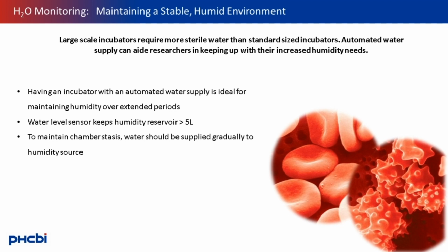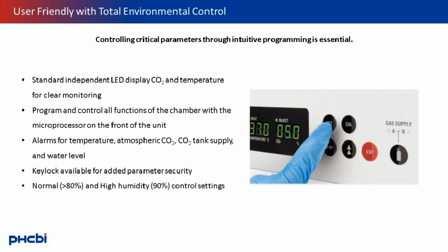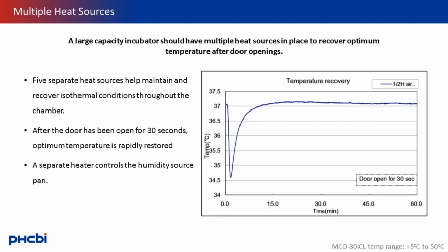Adjusting the levels for the humidity source can be done easily from the front of your incubator. It's important to be able to easily control the parameters of your incubator. Temperature, humidity, and CO2 can be controlled all in one place from the front of the incubator. CO2 and temperature display can be seen from across the lab, and standard alarms for temperature, chamber, CO2 tank supply, and water levels help safeguard optimum conditions in the incubator chamber. As well, a standard key lock for user security helps safeguard incubator set parameters.